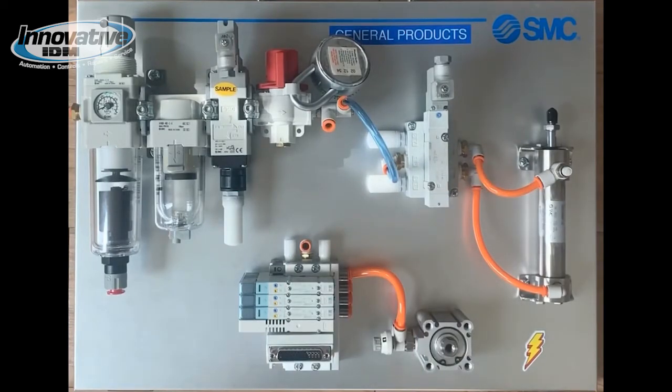Our top directional control valve is an SY 5-port valve which takes a control voltage of 110 as denoted there. It's piloting a stainless steel round style cylinder. Down below we have the new series SY solenoid valves mounted on a bar stock manifold. The bar stock manifold is extremely compact and features field replaceable cartridge fittings. This manifold is operated by a D-sub connector which can be routed back to a PLC.